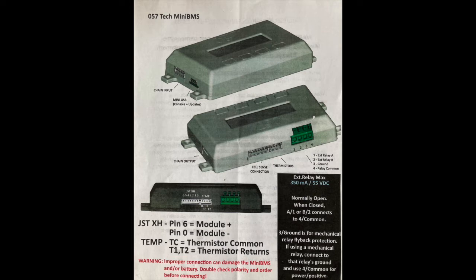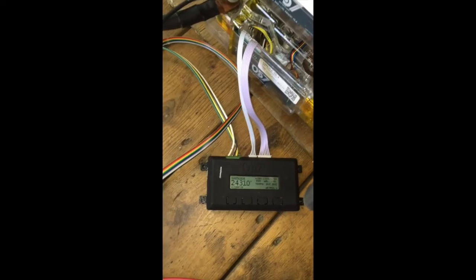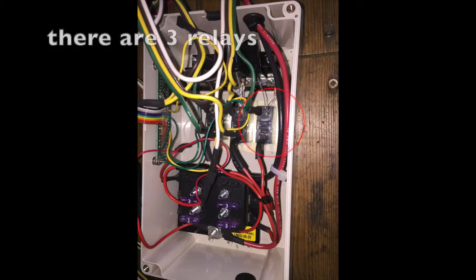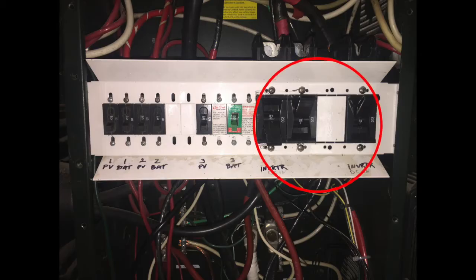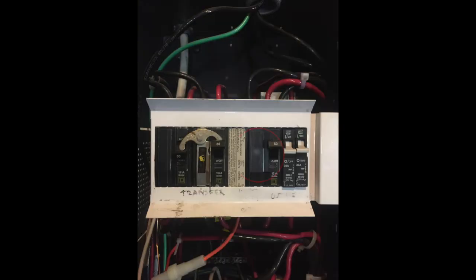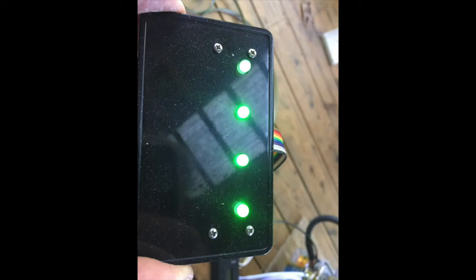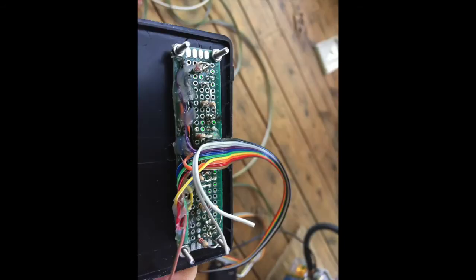So here's how the BMS works. Inside, there's a relay that sends a signal to whatever outboard control system you design. In this case, I used the output signal of the BMS to switch an external relay that has two functions. The most important function is to send a signal to the circuit breaker to turn off the charging source or the DC loads. The other function is to turn the appropriate green light to red on the LED monitor, signaling an event that requires attention.